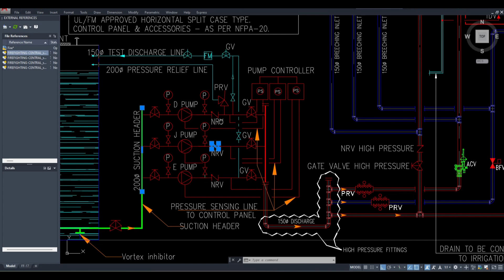So always after the pump we keep it, because we want to protect the pump. So what happens when the pump is in running mode, it is forcing water to go this side. But once the pump is closed, the water comes back, because you remember you have to maintain the pressure in this line. So once the pressure is done and this pump is closed, then this water, if it is pressurized, will tend to come backside. And once it comes backside, it will start rotating the pump in the opposite direction. Okay, and it will lose the pressure. Also, it will rotate the pump in the different direction. It will harm the pump mechanically.